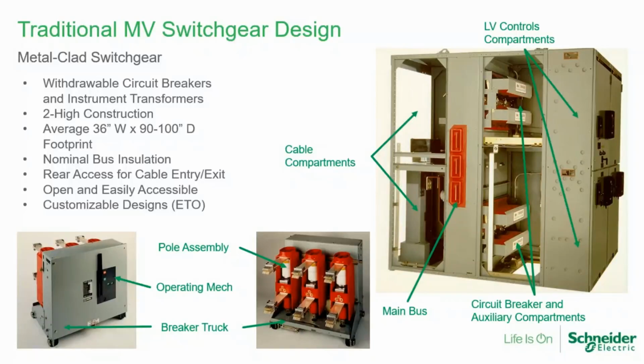But the big difference between the philosophies of ease of maintenance versus less maintenance, by having an open and exposed busing area and especially an open and exposed circuit breaker, means that the rear of that circuit breaker, the operating components of that circuit breaker, is open and exposed to environmental contaminants, things like moisture and dust, chemicals, rodents and snakes and things that like to crawl into switchgear to stay warm in the winter. All of these environmental considerations contribute to switchgear failures or switchgear lifetime degradation. That's the trade-off between ease of maintenance versus having a more enclosed style.